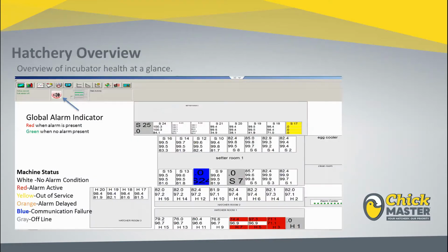We do this pretty simply with the hatchery overview, as you can see here. The hatchery overview screen allows the user the ability to see if there are any machines alarming. As you can see, I've got a couple machines down here in this bottom right area of the screen indicating alarms. Temperature and humidity alarms are shown. Any alarm at all will cause the machines to show up in red, and a zonal alarm will be indicated by what zone of the machine is highlighted, whereas a global alarm, something like a fan failure, for example, will be indicated as a whole machine turning red.